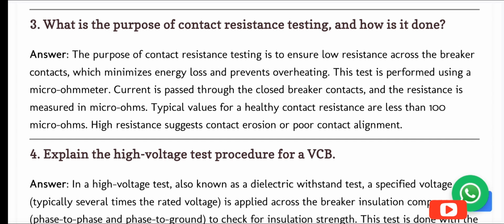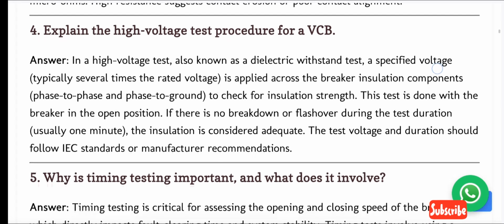Answer. The purpose of contact resistance testing is to ensure low resistance across the breaker contacts, which minimizes energy loss and prevents overheating. This test is performed using a micro-ohmmeter. Current is passed through the closed breaker contacts, and the resistance is measured in micro-ohms. Typical values for a healthy contact resistance are less than 100 micro-ohms. High resistance suggests contact erosion or poor contact alignment. 4. Explain the high voltage test procedure for a VCB.